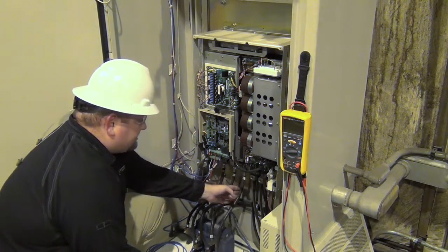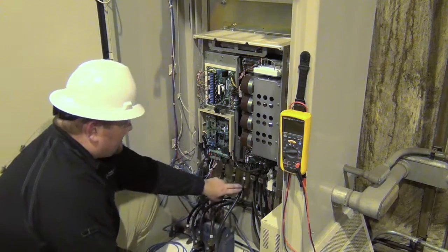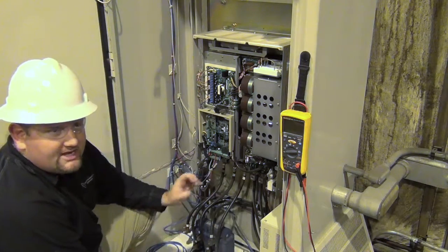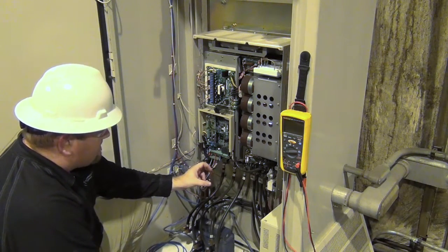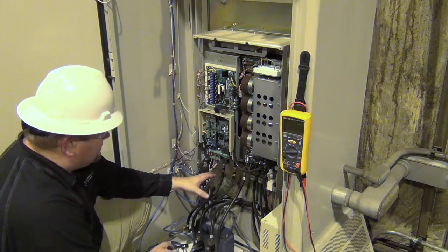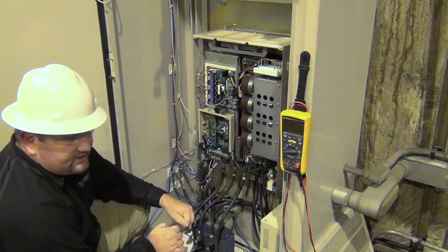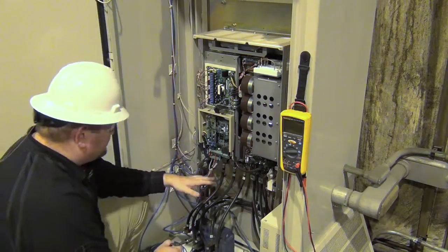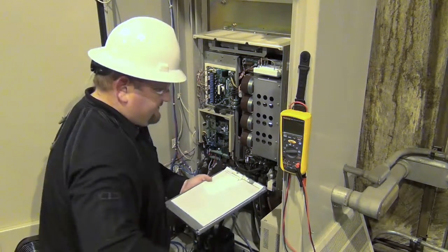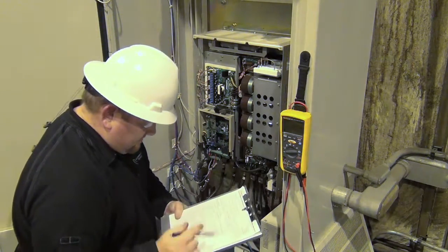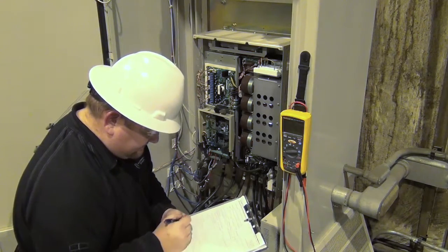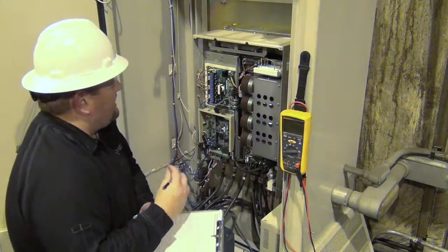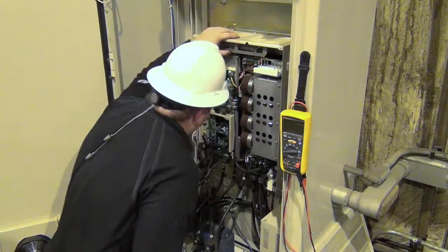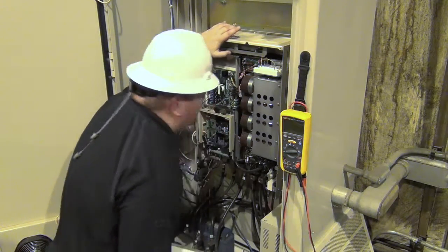If your installer has torque marked your equipment, a simple push test to make sure that it hasn't backed off and an inspection of the torque mark can substitute for this. Otherwise, what we recommend is just give it a little snug and make sure that it's not loose. So now that we've gone through those steps, we'll update our form. We've checked all of the mounting bolts. We've checked the cooling fan, made sure that there's no signs of heavy buildup on the blades.